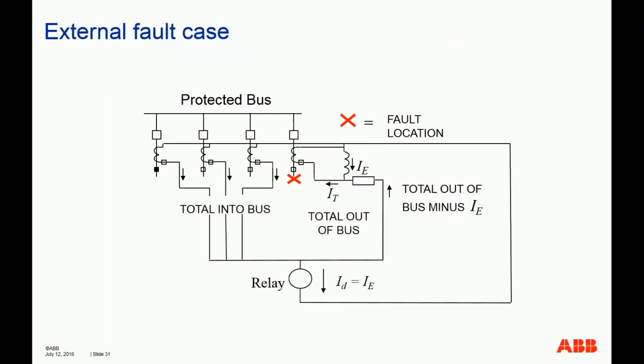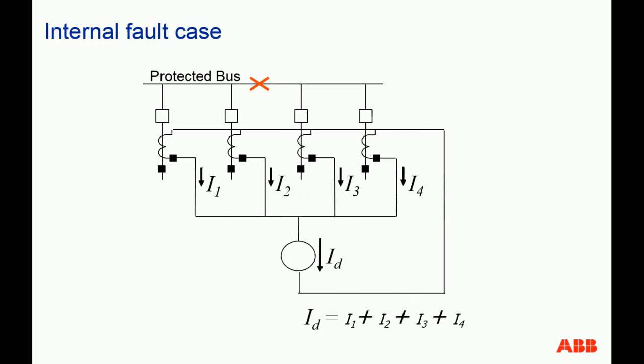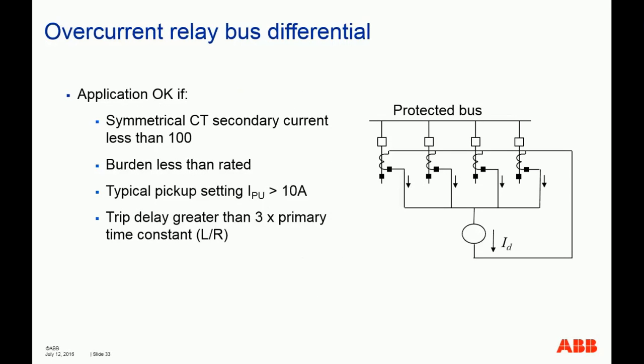Okay, the next two slides show that for an external fault, when the CT saturates, you will have excitation current flowing through the excitation branch, and assuming the other CTs are well behaved, that current becomes your false differential current. Your pickup needs to be higher than that, or otherwise your overcurrent relay will misoperate. An internal fault is basically the summation of currents that we all know. So the conclusion for this type of simple design: the prerequisite for using it is that you are very sure you have sized and specified your CT based on the fault level alone, and you are pretty sure there will be no chance of CT saturation, because the relay is not capable of dealing with CT saturation.